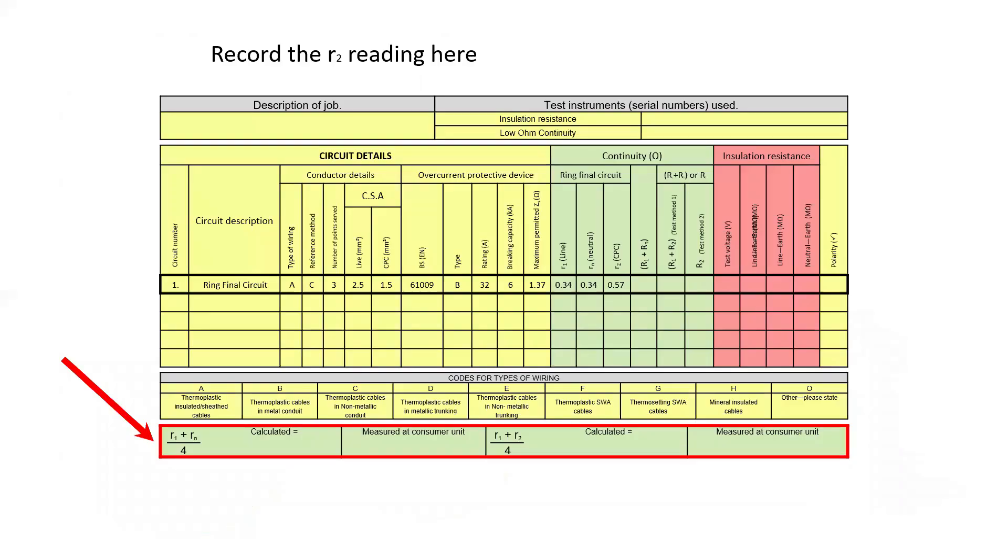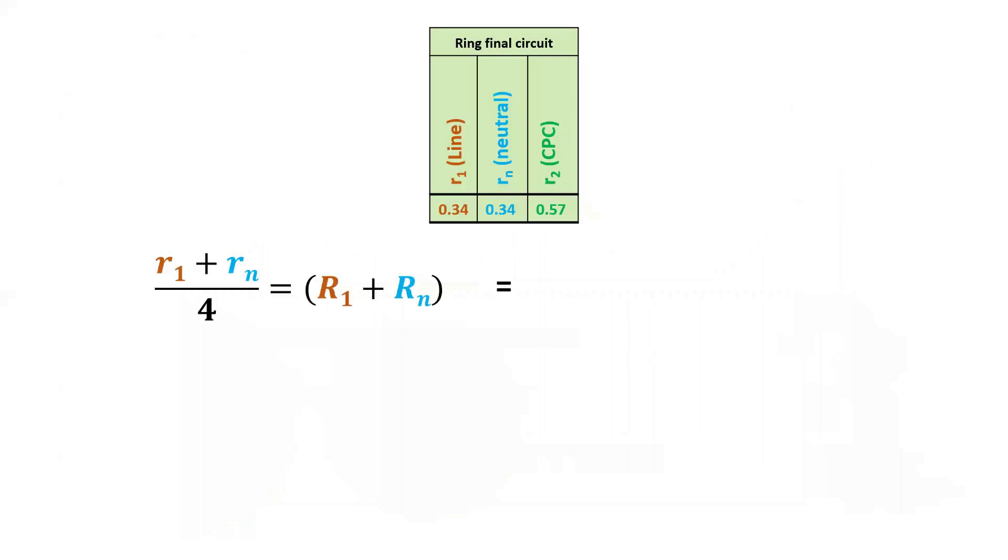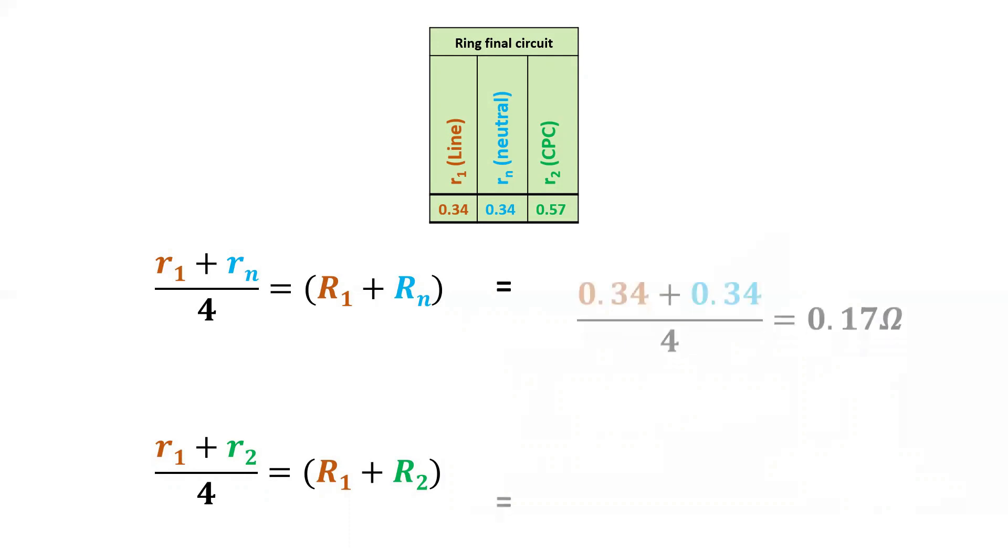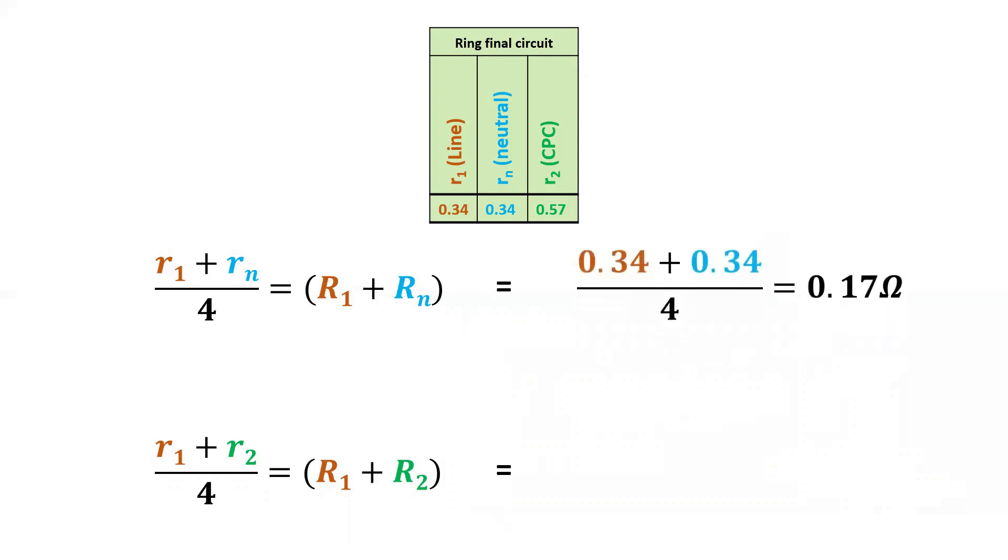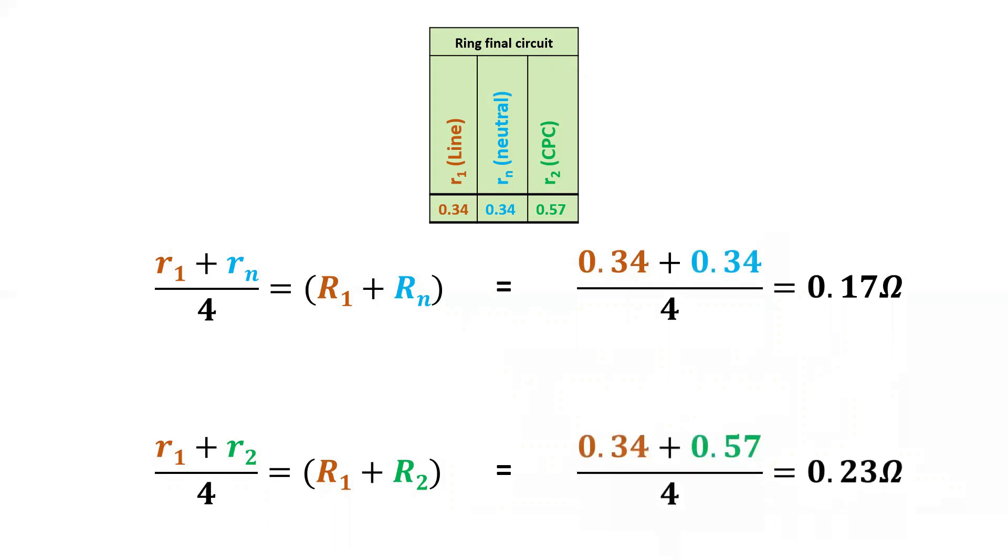At this point make sure you calculate the R1 plus Rn and the R1 plus R2 using those values. The two formulas you need to use are R1 plus Rn divided by 4 and R1 plus R2 divided by 4. If I put the values from the schedule into this formula we have an R1 plus Rn of 0.17 ohms and an R1 R2 of 0.23 ohms. This now tells us what value of resistance we should be expecting at each point on the ring final circuit that we are testing, unless it's a spur or there's an interconnecting fault.